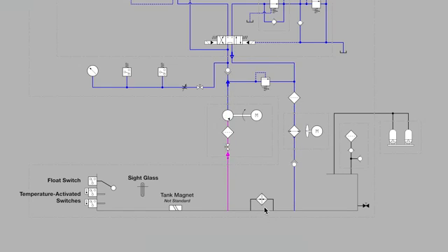Moving over, we see a diamond shape. Anytime a symbol has the diamond, it indicates a fluid conditioning device of some kind, and in this case, with the dark arrows pointed inward, it lets us know that this is a heating device. It brings heat into the fluid in the tank, and the dark black lines on each side of the diamond indicate that fluid is used to heat and exchange with the fluid in the tank, but the plumbing for the heating system is external and not shown.